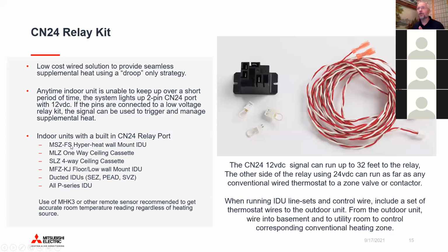And as I mentioned earlier, it's applicable for most Mitsubishi equipment, right? So the FS are our deluxe hyperheat products. Our MLZs are the one-way ceiling cassettes, SLZs, four-way ceiling cassettes, the floor models. All of our ducted models have CN24. In fact, all of our ducted models have two CN24s, CN24 1 and 2, so you can have two stages of backup heat if you really wanted. And every single one of our P-series indoor units has it. What's glaringly missing from this list? It's the GLs. So our GL wall-mounted units do not have a CN24 port or ability to set it up.